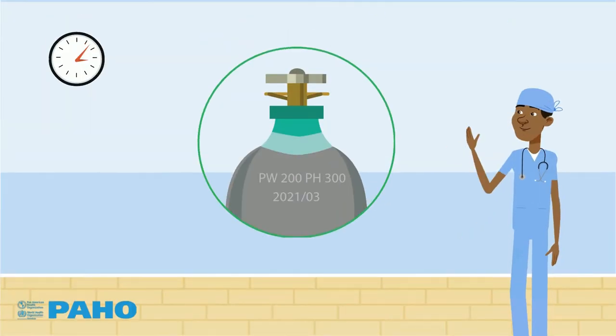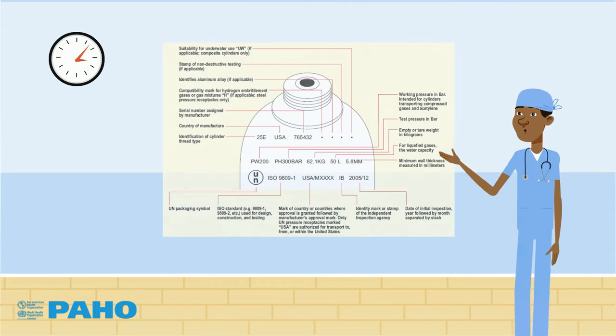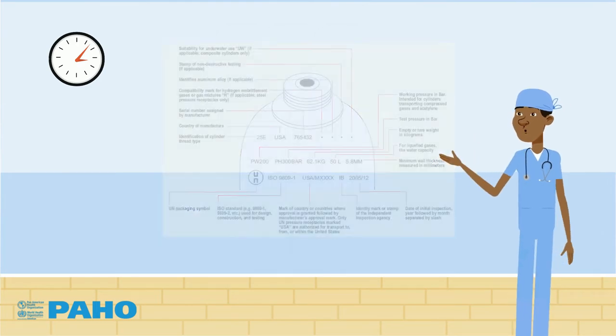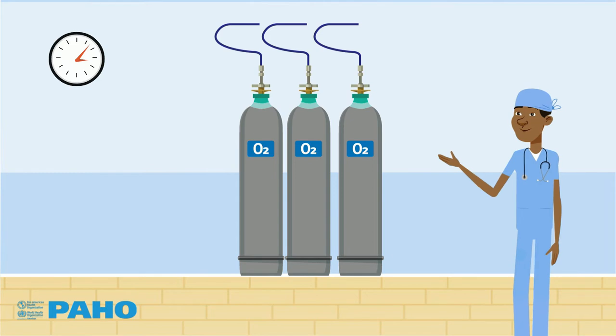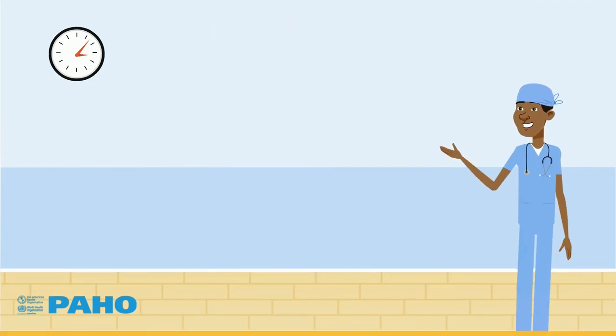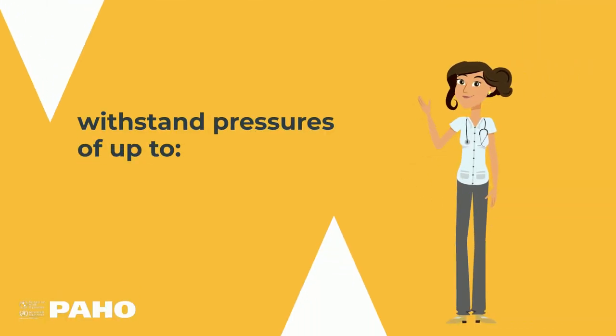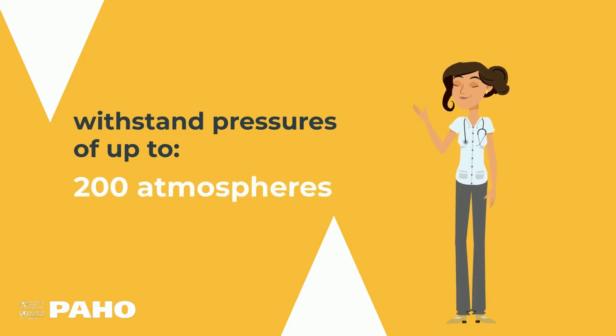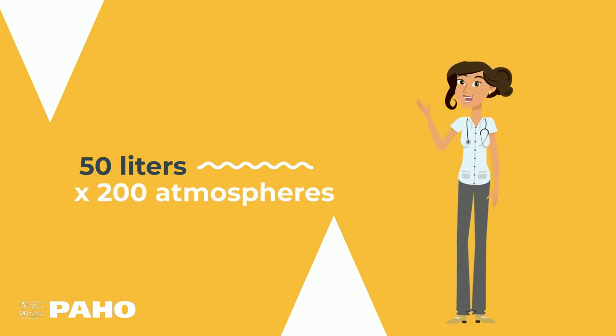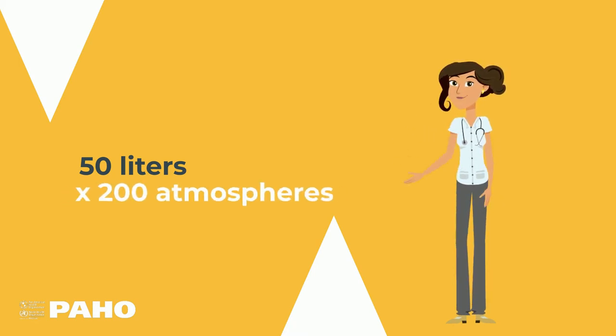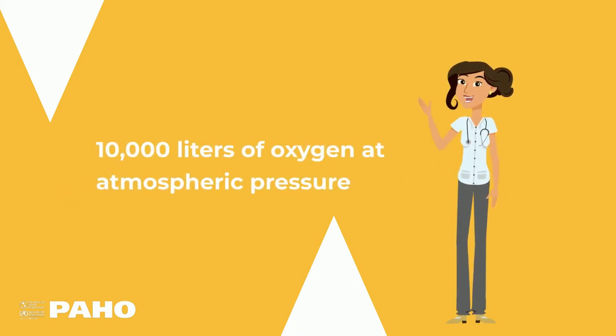The working pressure is also important because it allows the manufacturer to correctly determine the mechanical strength that the cylinder requires and to calculate the amount of gas it can store. Cylinders commonly withstand pressures of up to 200 atmospheres. If the cylinder has 50 liters of internal volume, multiplying 200 atmospheres by 50 liters tells us that we will have 10,000 liters of oxygen at atmospheric pressure inside the cylinder.